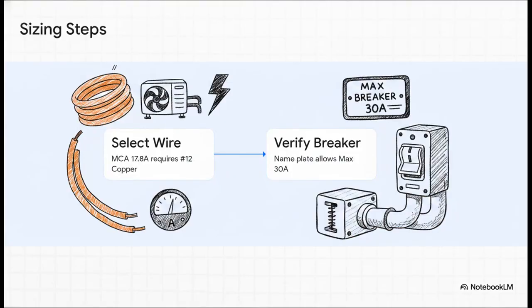So the crucial point is how these two steps actually come together. Step 1, select the conductor. We know we need number 12 copper wire to handle the 17.8 amps. Step 2, verify the circuit breaker. The nameplate explicitly allows a maximum circuit breaker of 30 amps, so we're going to pair our number 12 wire with a 30 amp breaker.